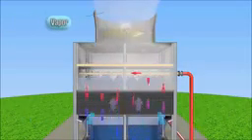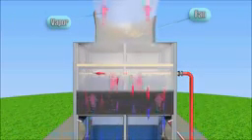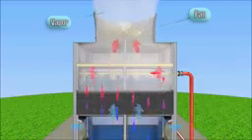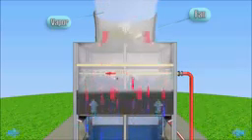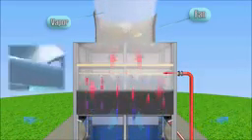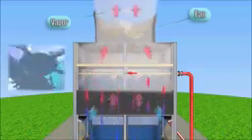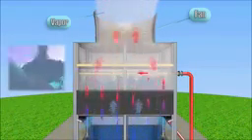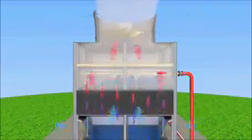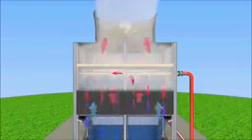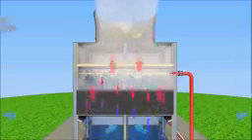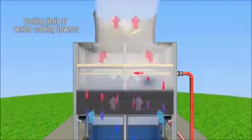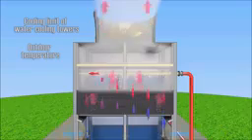With the help of the fan, a steady airflow with low humidity is fed. The air passes through the fills, saturated with water vapor. The water cooling efficiency of fan cooling towers may be controlled by varying the supply of air, changing the fan speed. A theoretically ideal loss is the work to convert the water to steam. The limit of cooling water in the cooling tower is the temperature of the outside air, the wet bulb temperature.